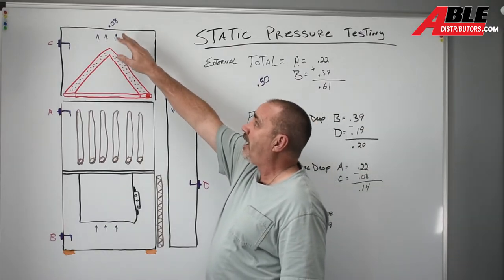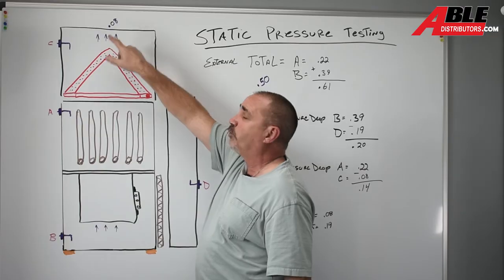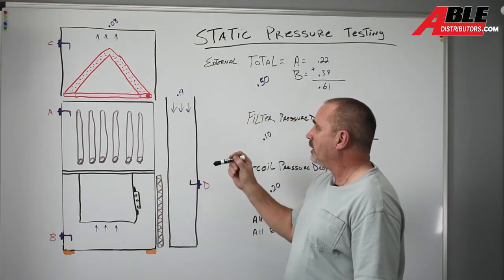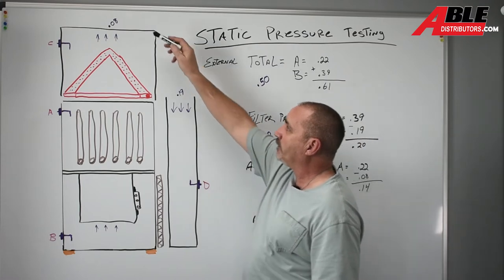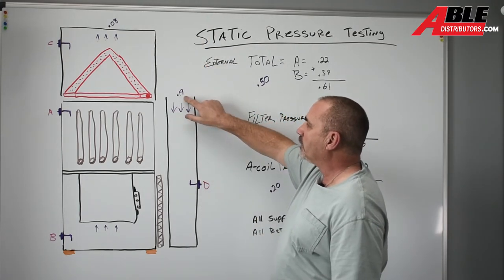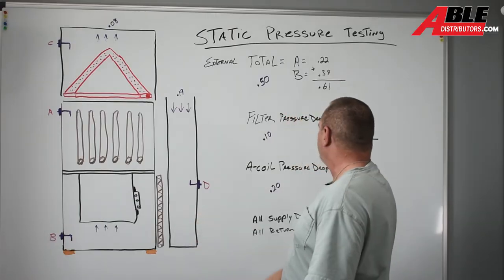And that also tells me that every single thing, every ounce of duct work past that, the static is 0.08, so that's pretty low. So now if you look at what we've done here, we can tell you now that the duct work on the supply is plenty good at 0.08. The duct work on the return at 0.19 and the filter at a 0.20, those are our issues.